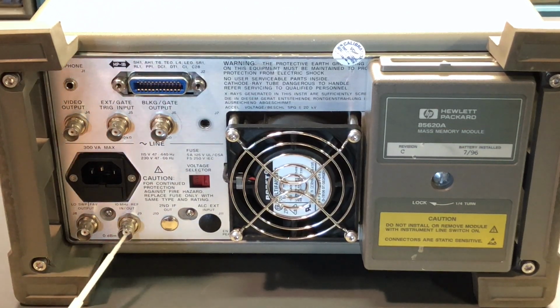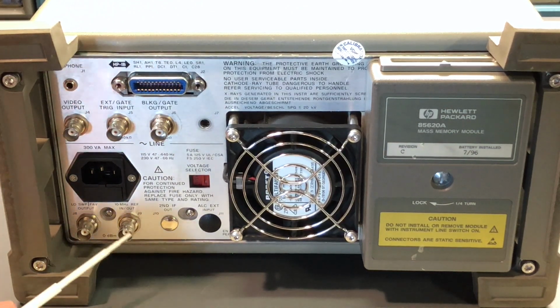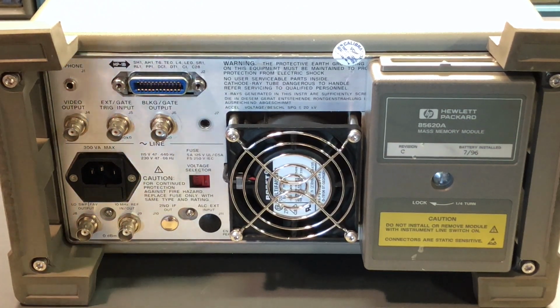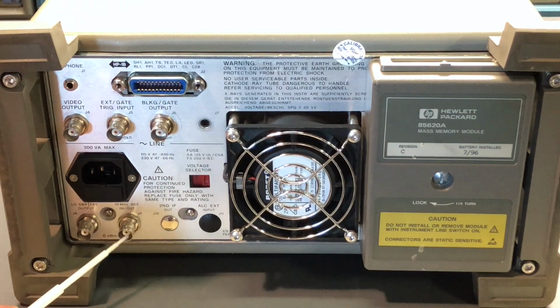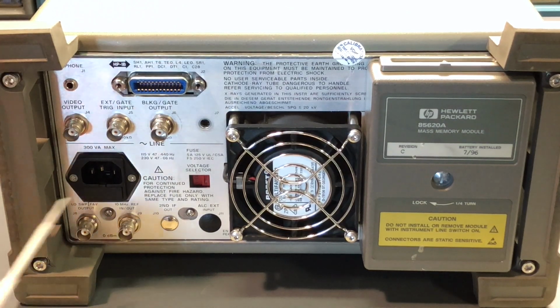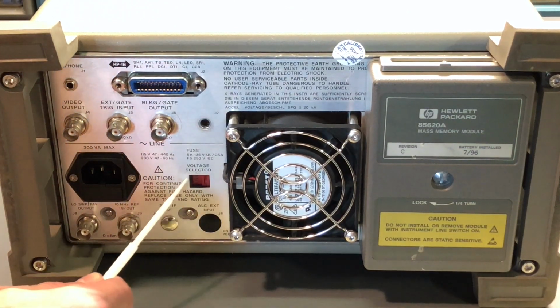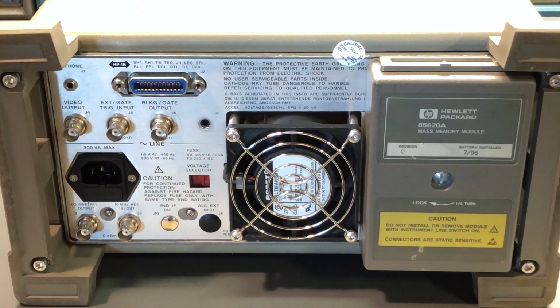Right here, this is a 10 megahertz reference in and out. So if you're using the internal standard, this will output a 10 megahertz signal. But if you want to input a 10 megahertz signal right here from an external standard, you can certainly do that, and it'll override the internal frequency standard. Of course, the AC input right here, and the voltage selector right here for the AC input.